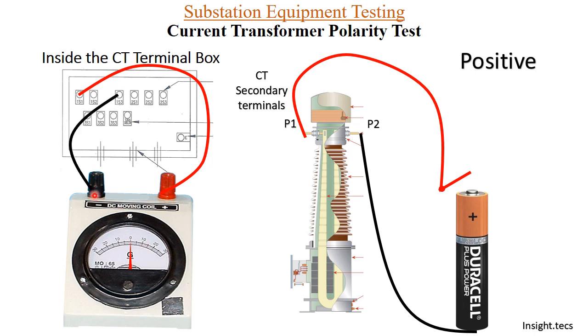Whenever the ratio is connected at 600/1, we connect 1S3 to the negative terminal and 1S1 to the positive terminal. When P1 is connected, the deflection will be on the positive side — confirming that with this ratio also the CT polarity test result is positive.